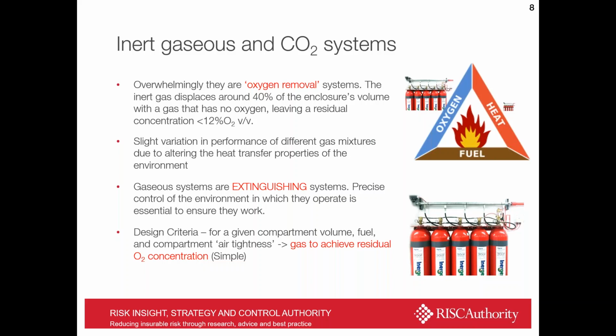When you inject these gases, if 40% of the compartment's volume needs to exit, it needs to do that in a means which is controlled to an appropriate location and doesn't raise pressures inappropriately. And then having discharged it, there needs to be mechanisms to seal the enclosure and ensure that you can hold on to that gas quantity. At the end of the day, these are quite highly developed systems. Again, the design criteria are very simple. For any given compartment volume and type of fuel and compartment air tightness, it looks at just the amount of gas required to achieve a residual oxygen concentration, which is appropriate to the fuel being protected.